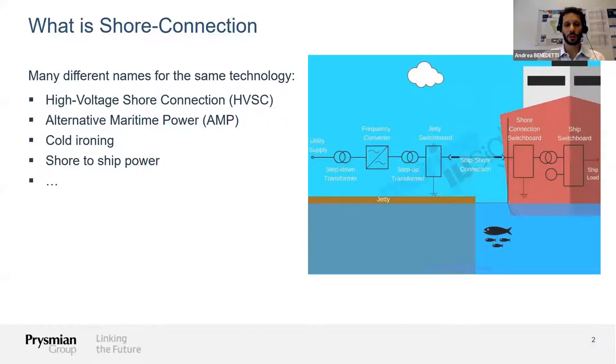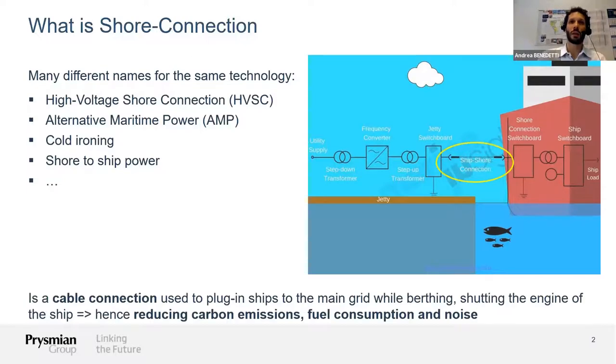First of all, I want to take a step back and define what terms we are discussing today. What is shore connection? For those who do not know this technology yet, it comes under different names: high voltage shore connection, alternative maritime power, cold ironing, or shore-to-ship power. These are all different names for the same technology serving the same purpose — to connect the ship to the main grid while the ship is at berth, and to provide the energy demand to the ship from the grid instead of using the diesel engines, so the ship can shut down its diesel engines and get the needed power from the main grid.